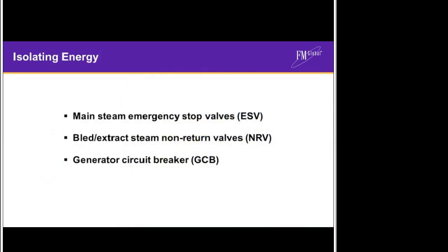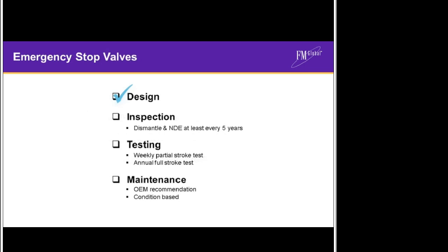As previously noted, fault detection on modern machines is generally very reliable. So the implication is that all five factors, design, inspection, testing, maintenance and operators, are well implemented. So then the focus moves on to the tripping devices themselves. In the case of energy isolation, there are three potential sources of energy: the main steam supply, the bled or extract steam, and the electricity network, which the generator is connected to. The design of modern emergency stop valves is generally a good news story. If operated within their design envelopes, they last well between outages and operate reliably. They also generally allow testing whilst the turbine is online.